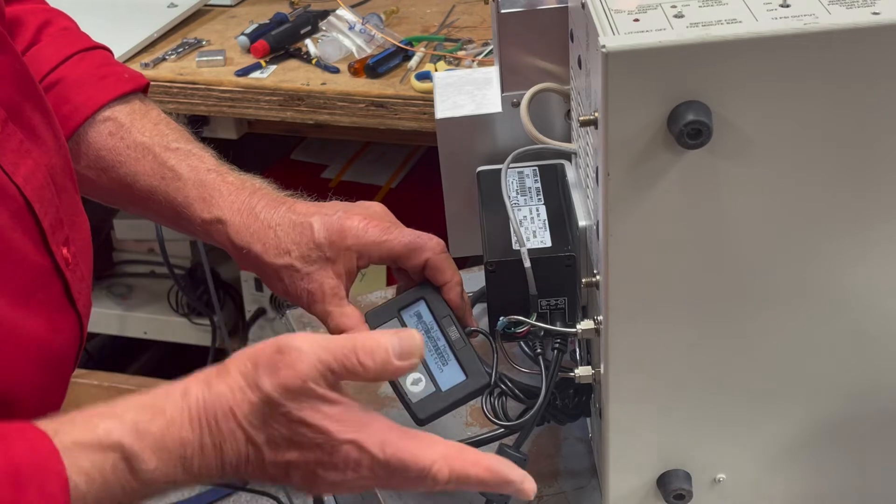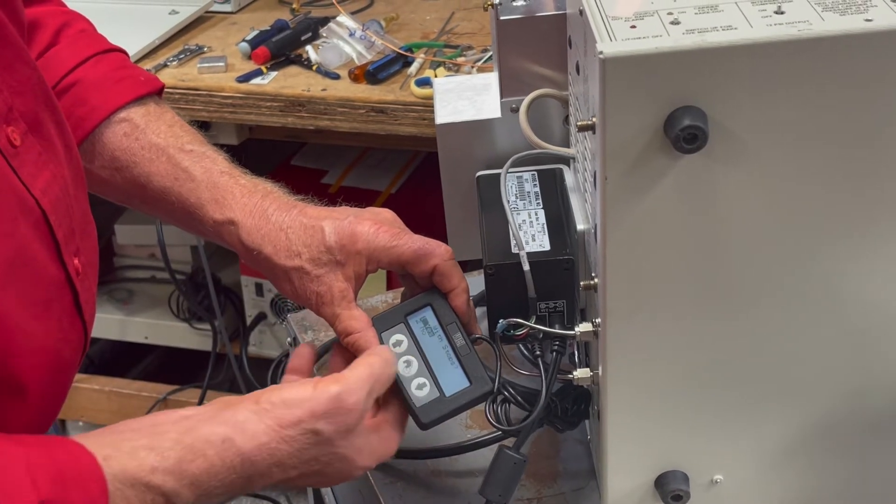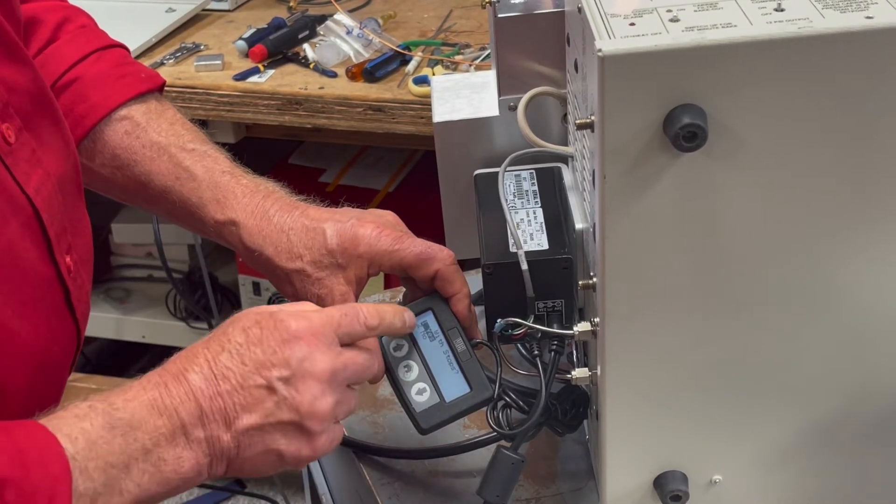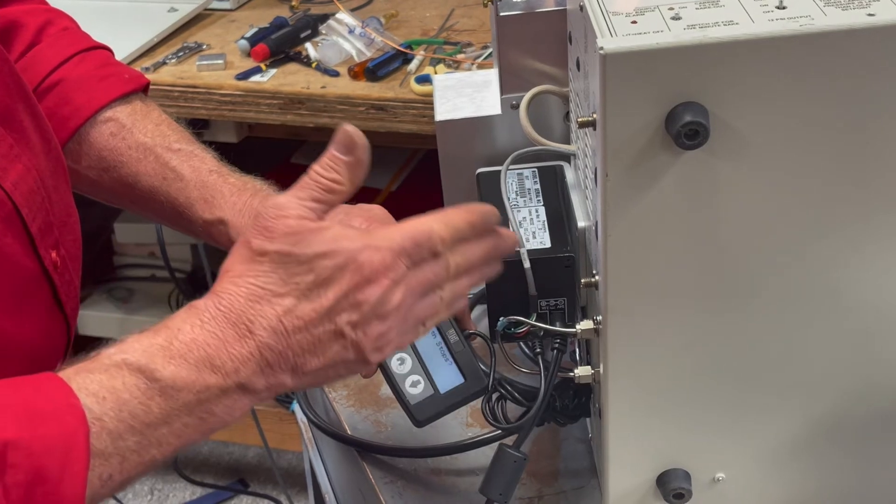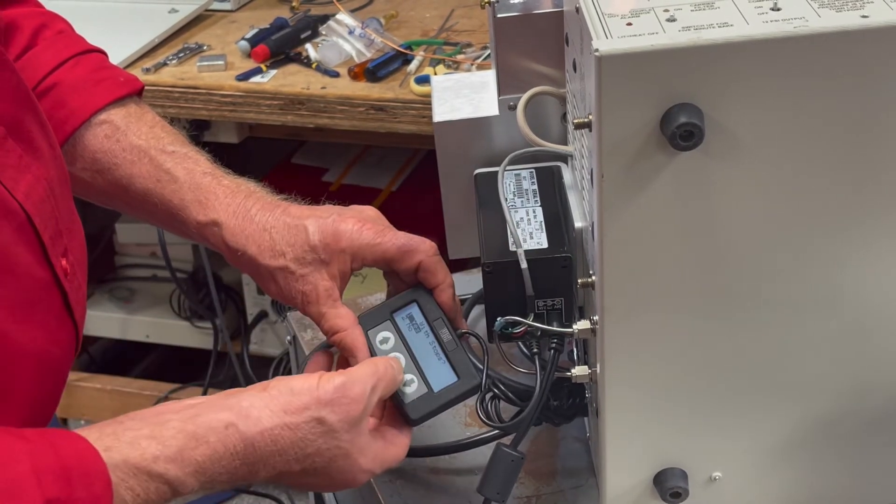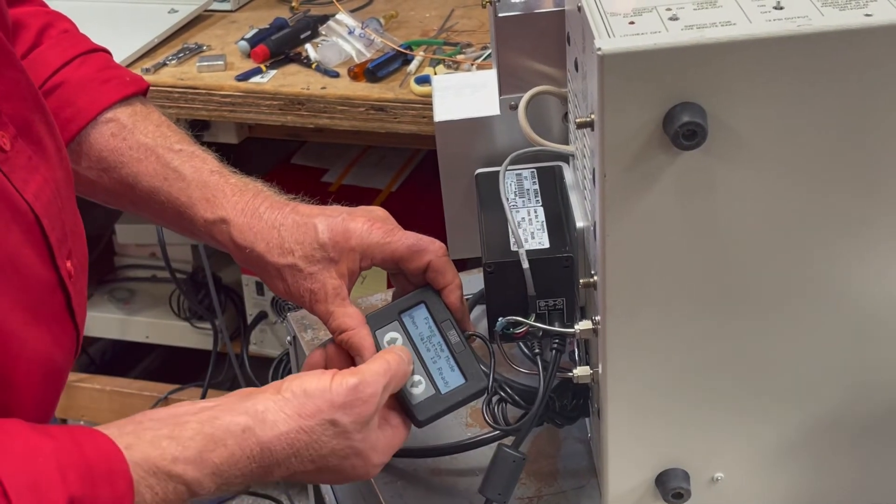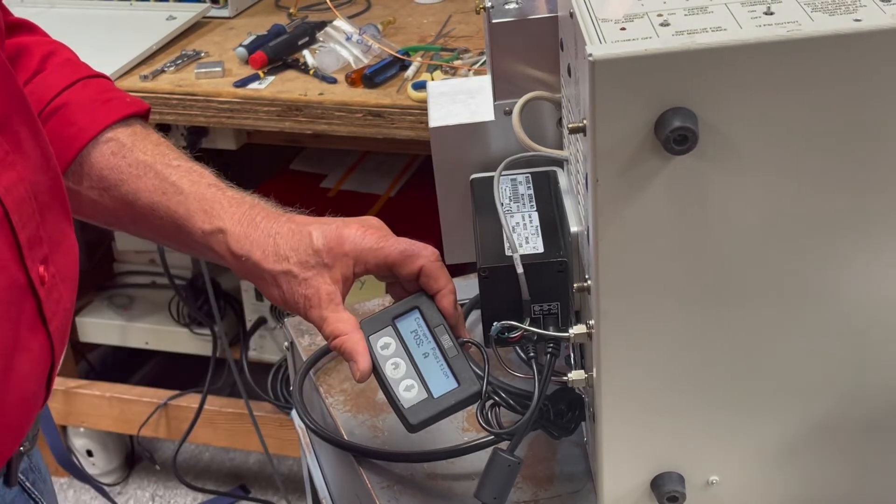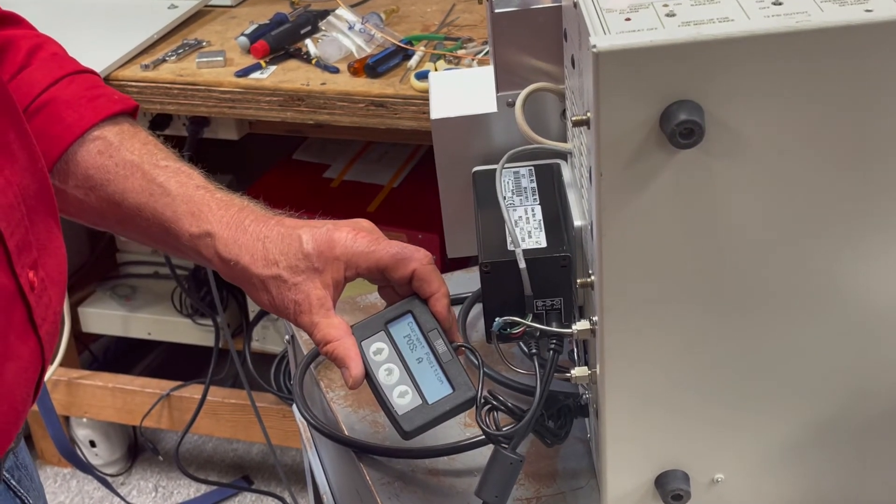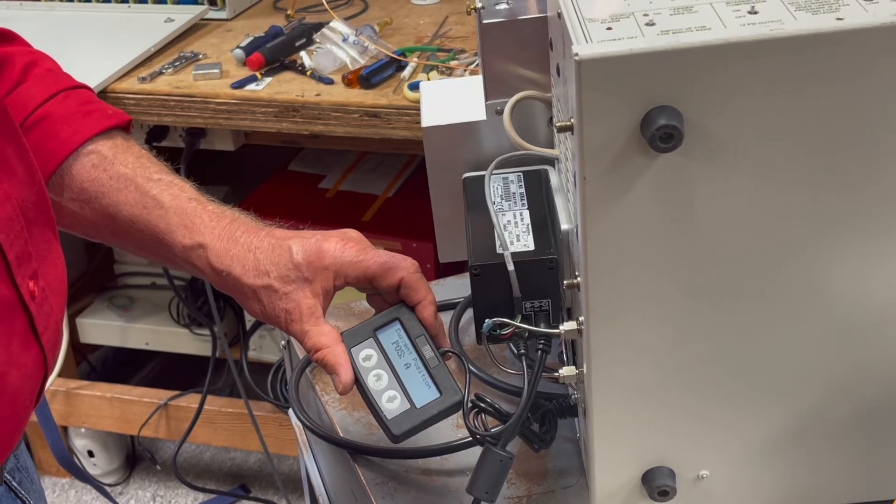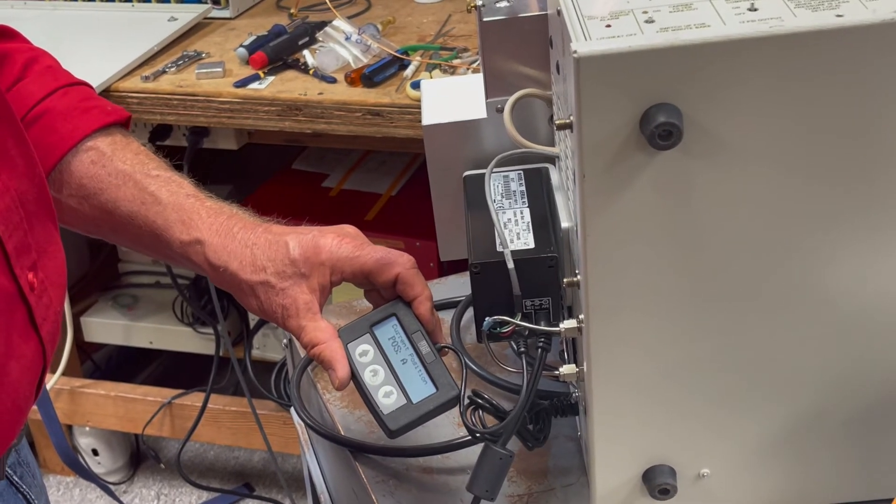These are just two positions, one way or the other. So you say yes, and then with stops, yes, because that's what we want it to do is figure out where the stops are on the valve. And then you hit OK, and then it goes through its little learning routine. It's a little louder, but that was quicker.